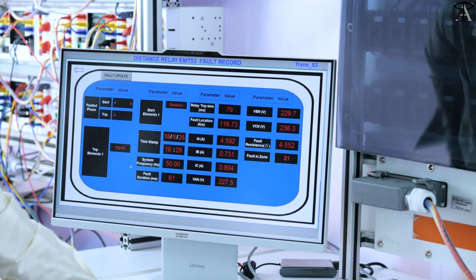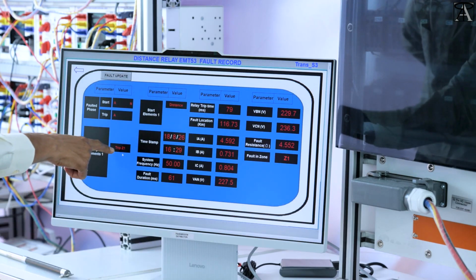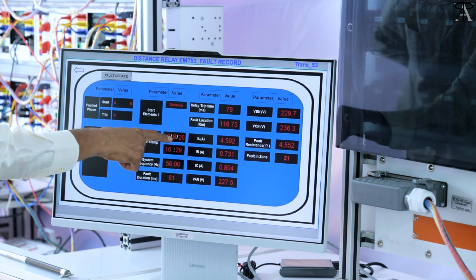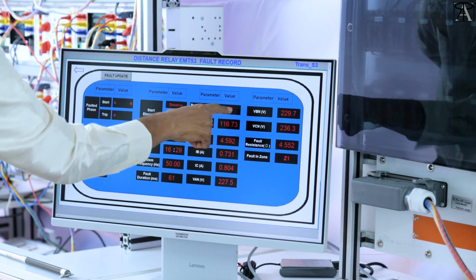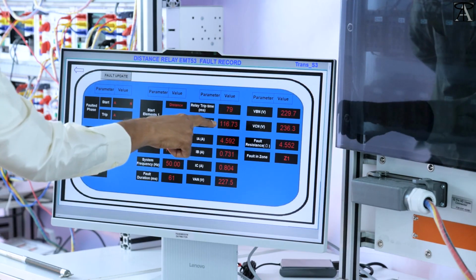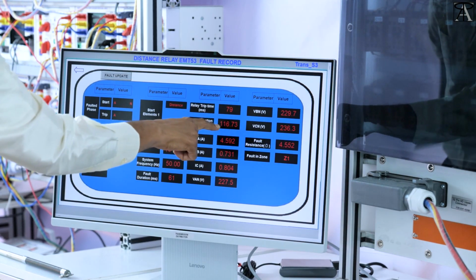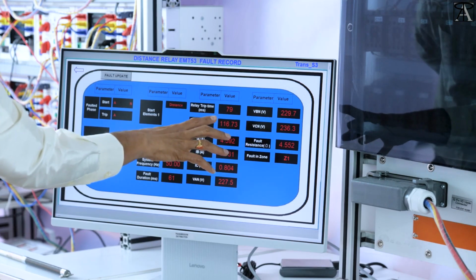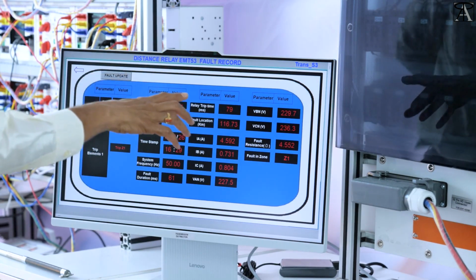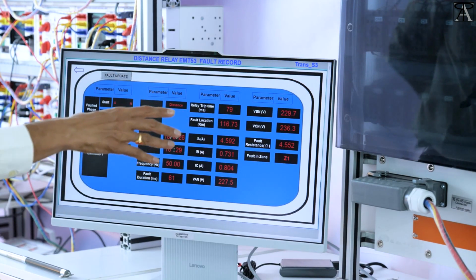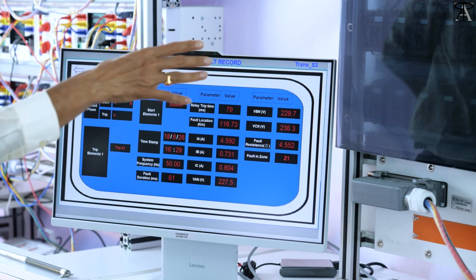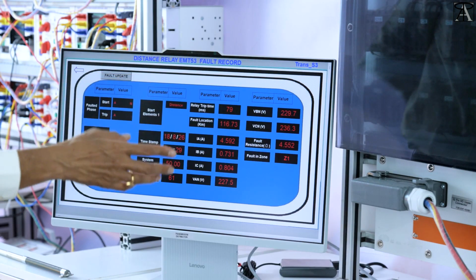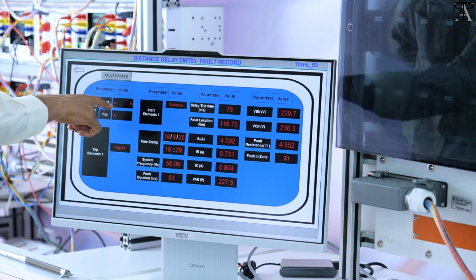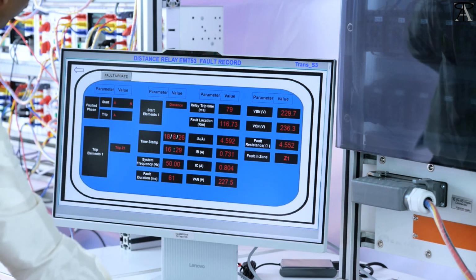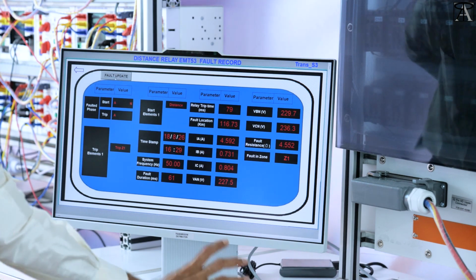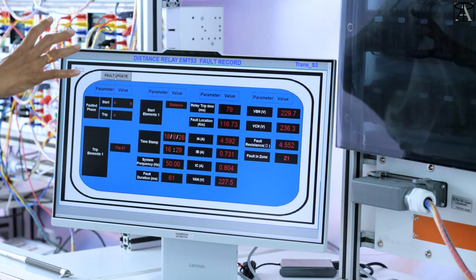And here trip zone 1 fault. Here you can see trip zone 1, time, date, and relay trip time in milliseconds. Fault location, we have created fault in 125 kilometers. It is showing 116.73. Very accurately it is showing kilometers, so that the lineman can check near 125 kilometers and rectify the fault. And start trip, neutral, and one phase, A phase. You can see the timestamp in our SCADA software.